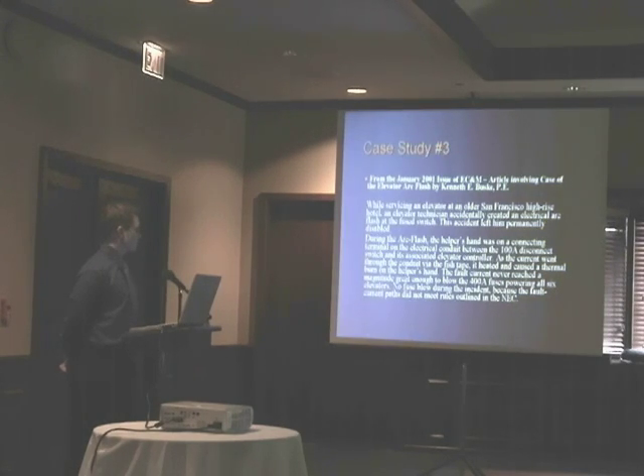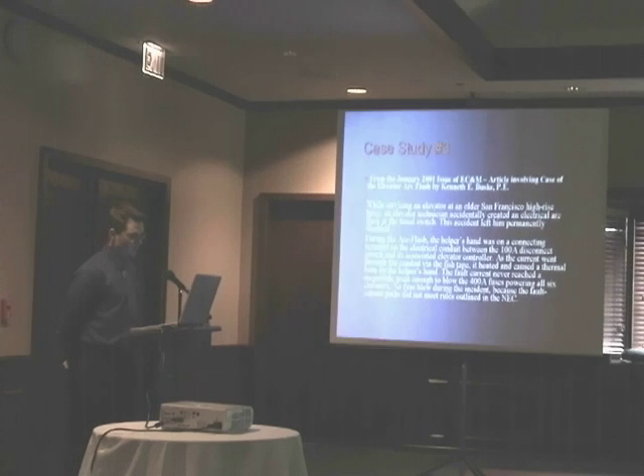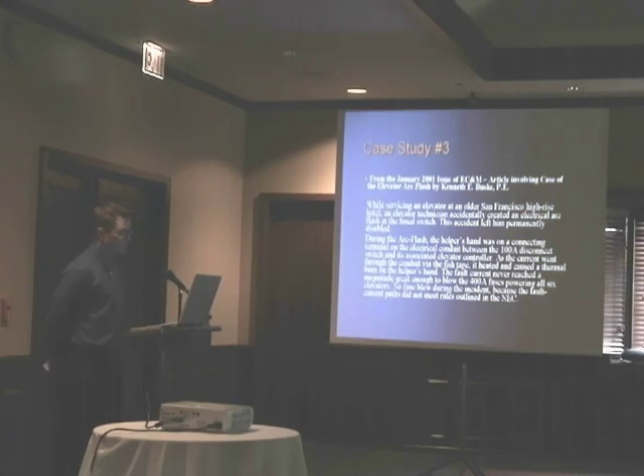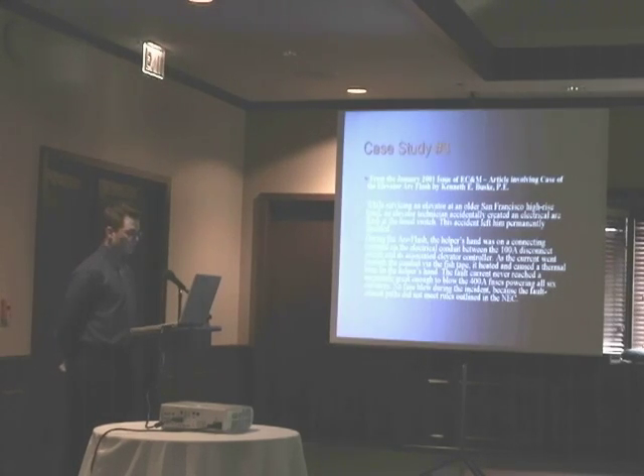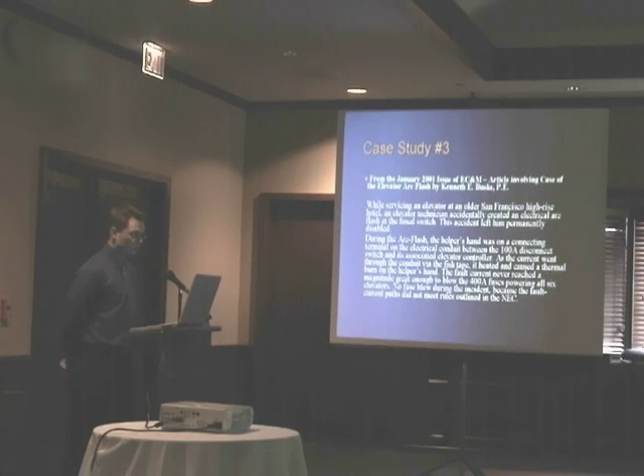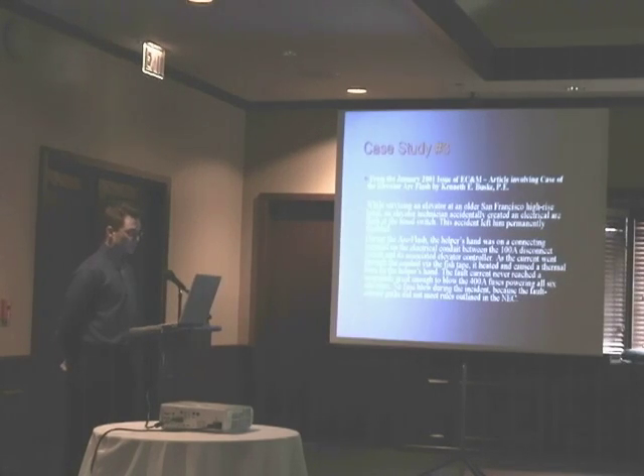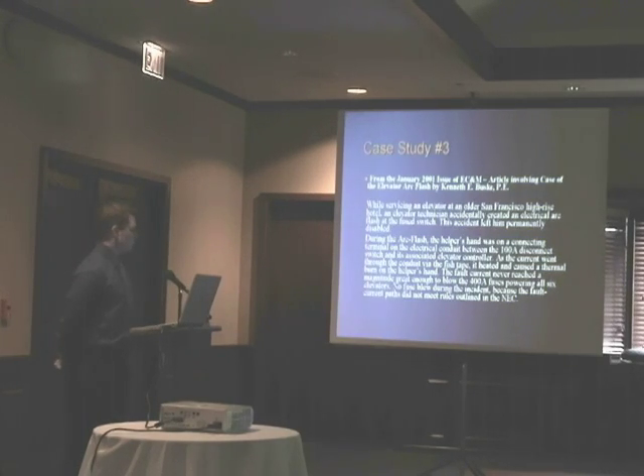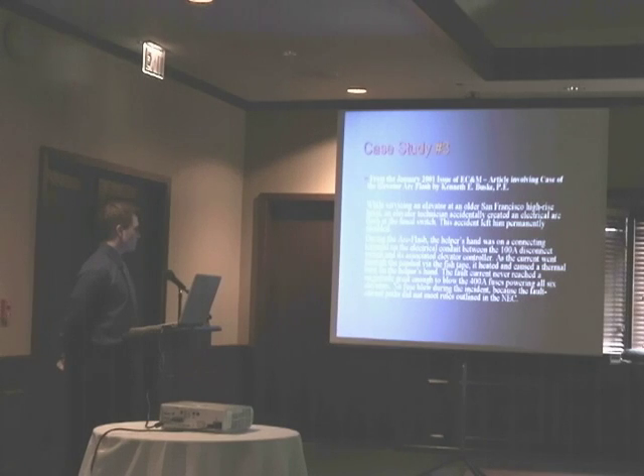During the arc flash, the helper's hand was on a connecting terminal on the electrical conduit between a 100-amp disconnect switch and its associated elevator controller. As the current went through the conduit via the fish tape, it heated and caused a thermal burn on the helper's hand. The fault current never reached a magnitude great enough to blow the 400-amp fuse powering all 6 elevators. No fuse blew during this incident because the fault current paths did not meet rules outlined in the NEC.